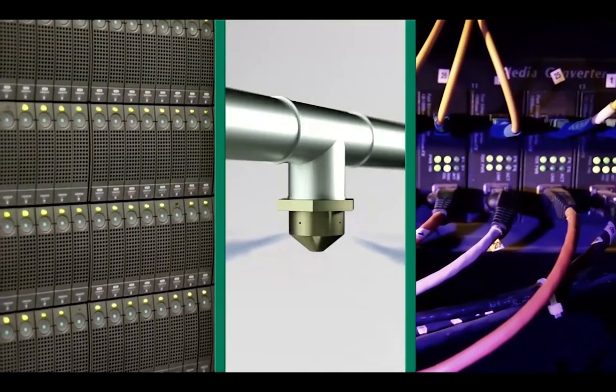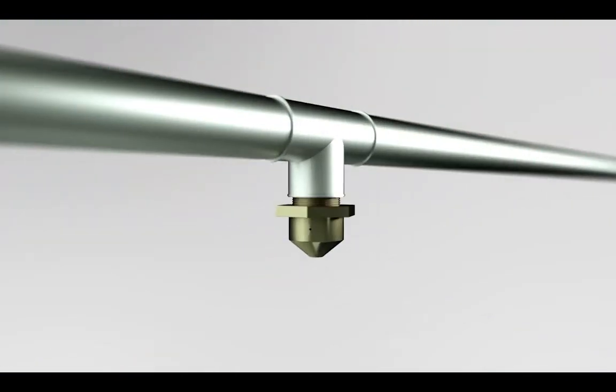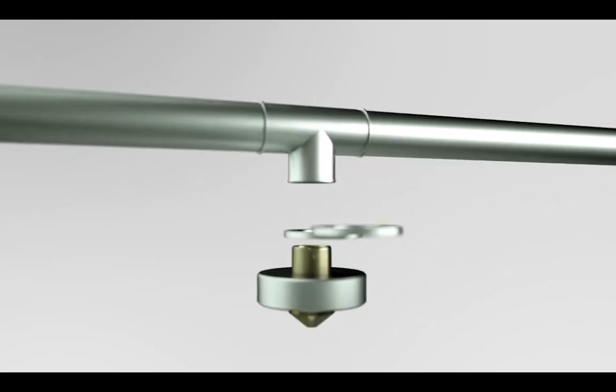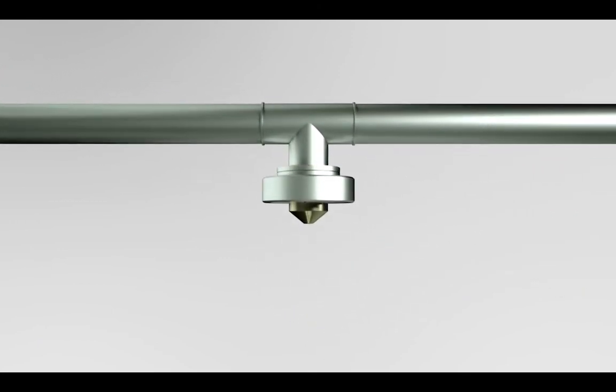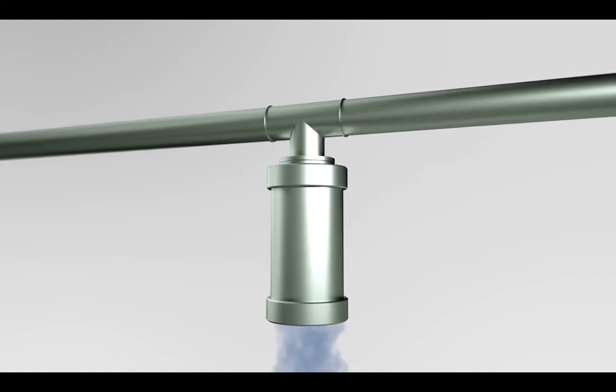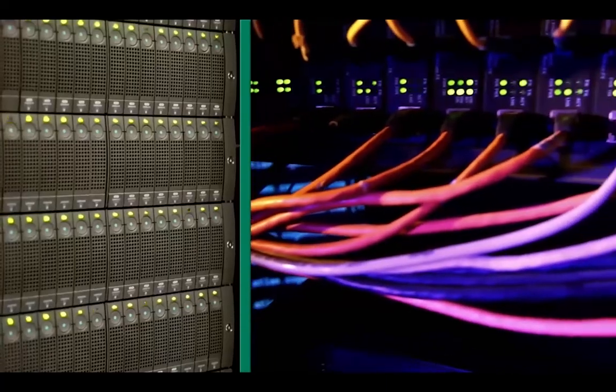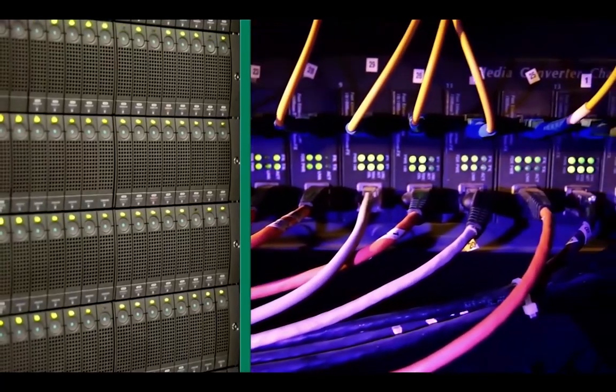Harsh vibrations from rapid outflow of nitrogen from the nozzle cause sound pressure of over 130 decibels. Our silent sound suppressor reduces the sound pressure level by up to 39 decibels. This makes us the first manufacturer to offer a solution which protects hard disks and other noise-sensitive components.